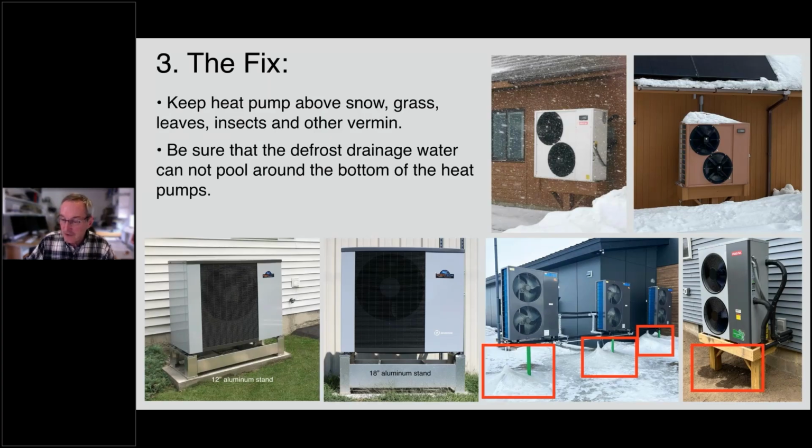Here's another one over on the lower right. You can see this water stain on the grate here. This is from the water that's drained out during a defrost cycle. And that unit is up high enough that, even in the wintertime, that water can drain out of there.